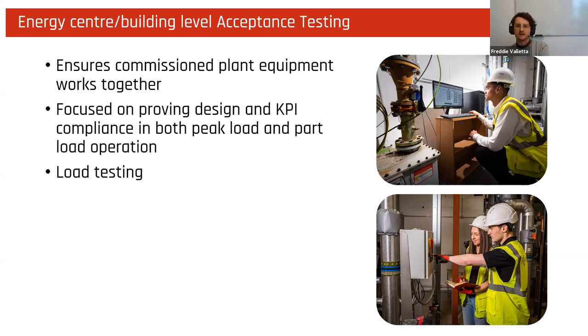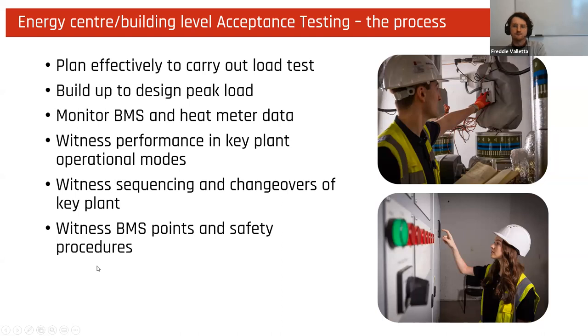We'll go through the whole process on the next slide. However, carrying out these load tests on the plant room ensures that design and KPIs are met under these varying loads, and ensuring the system operates correctly and as a cohesive unit. So yeah, load testing is able to prove this operation for both phased and whole developments.